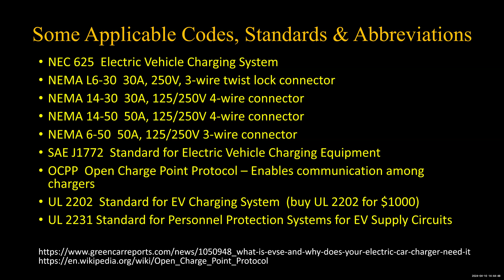So what if we want to add a charger? And this is what you might do for a single family residence, okay? And we're going to go through the calculation here. The old faithful 3 volt amps per square foot for a 1,500 square foot residence. We got 4,500 volt amps.